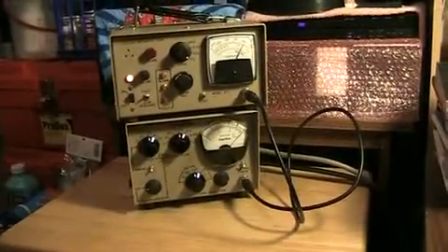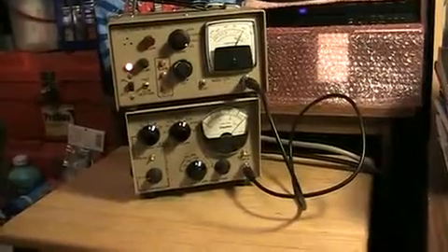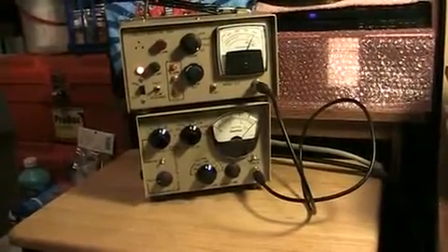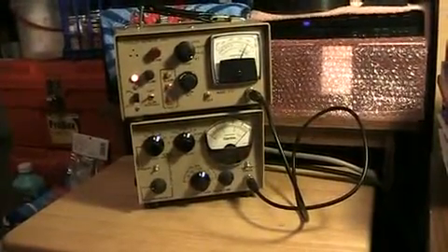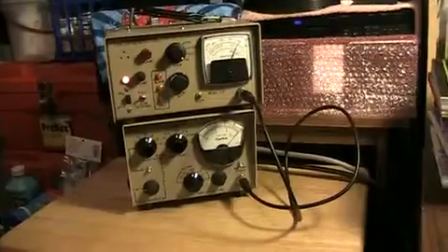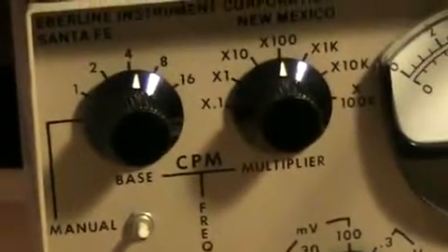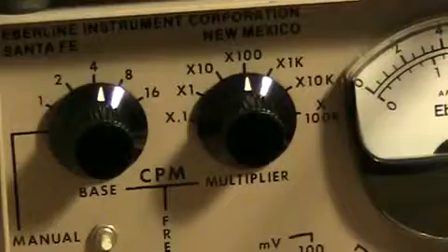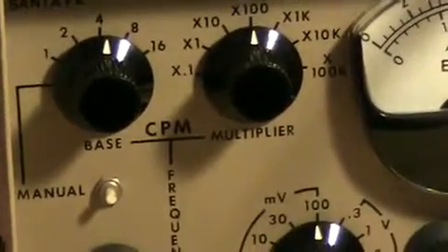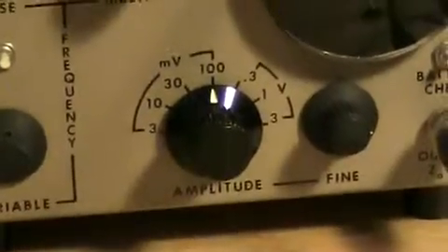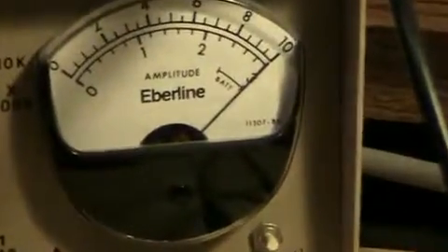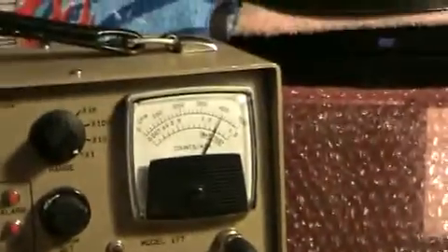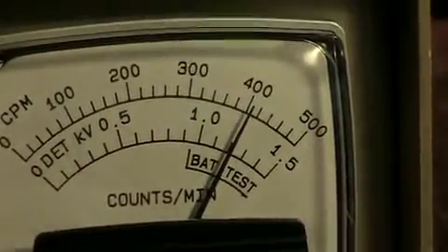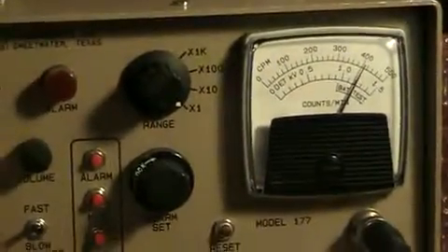It's going to be a little short video on calibration. On the bottom I've got the MP2 mini pulsar, and on the top my Ludlum 177. And the two are connected via the BNC. Let me zoom in here. This is set right now on 400 counts per minute, and set for 100 millivolt input, and that's right there, full scale, 100 millivolt. And we go up here and look at the input, and right there's 400 counts per minute. And this is set on the ×1 scale.